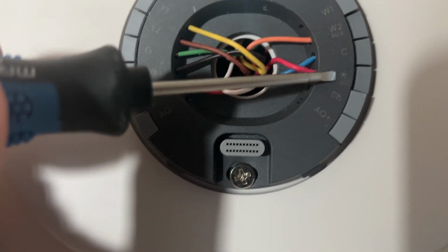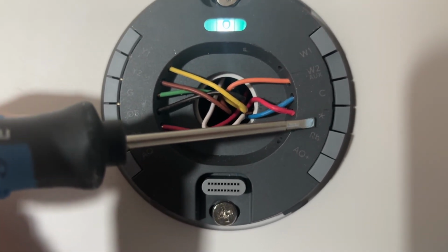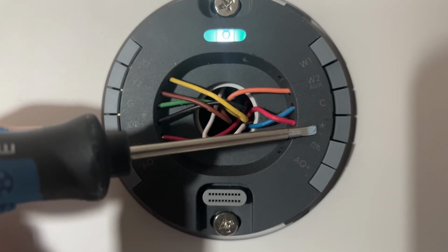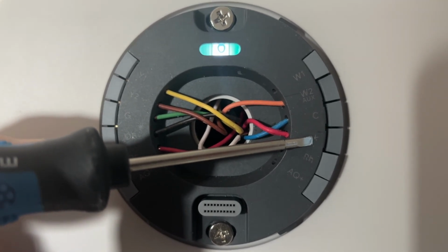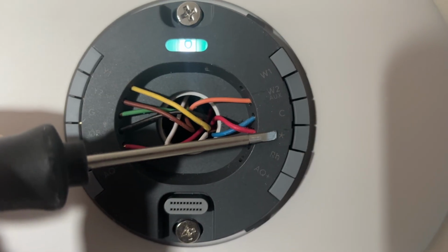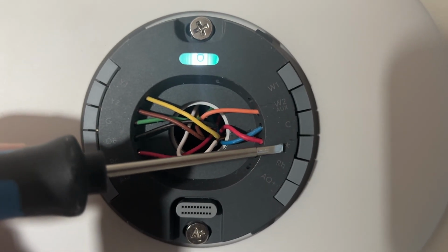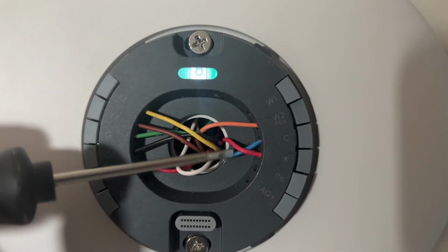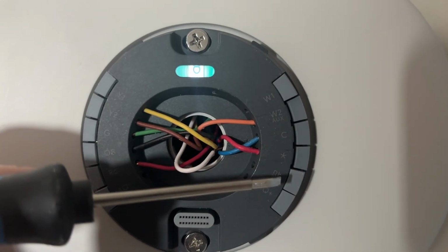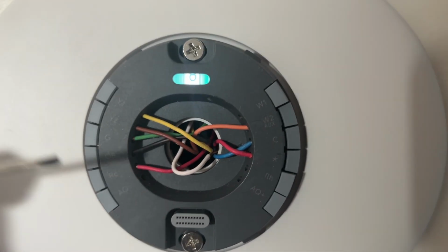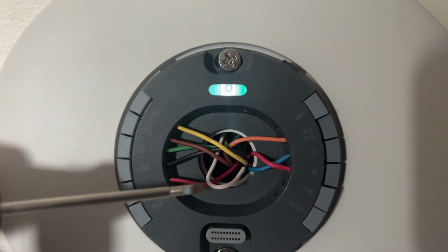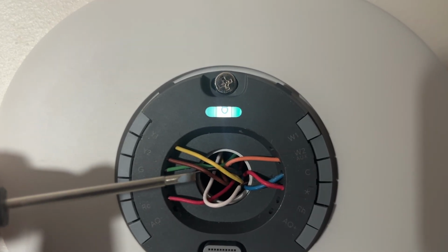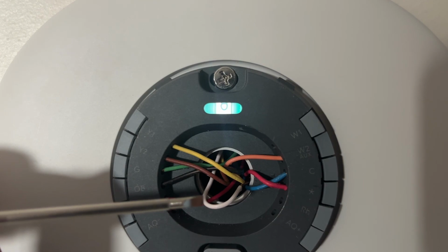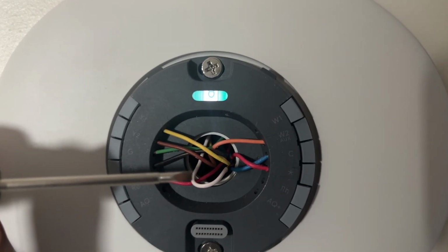And then we have our star here, which is the control for the dehumidifier. You can configure this hookup for different pieces of equipment. Mine is the Santa Fe 70. So we have that wire hooked in there to control that piece of equipment as well. And that's the gist of the wiring. So we have 8 wires in here and 7 hooked up into the air handler. And we have 2 hooked up to the dehumidifier.